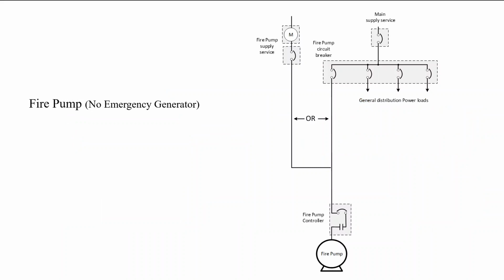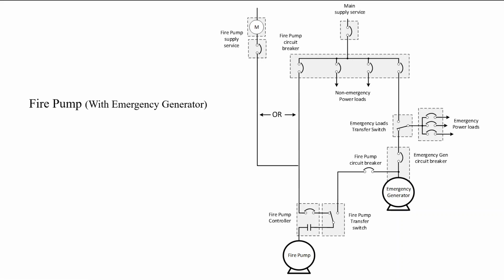If we take a look at the single line diagram for a standard fire pump, we'll notice the fire pump controller ahead of the fire pump with its overcurrent and power contacts at the very bottom there. And it can be supplied power either from the main building supply service off the distribution or a separate fire pump supply service. In a larger assembly or system where we have essential loads for life safety, often there's an emergency generator on site. The emergency generator is going to supply power to not only emergency power loads, such as emergency lights and maybe life safety equipment or equipment in a hospital, elevators, things like that, through its transfer switch, but it will also supply power to a transfer switch for a fire pump if it is on site.